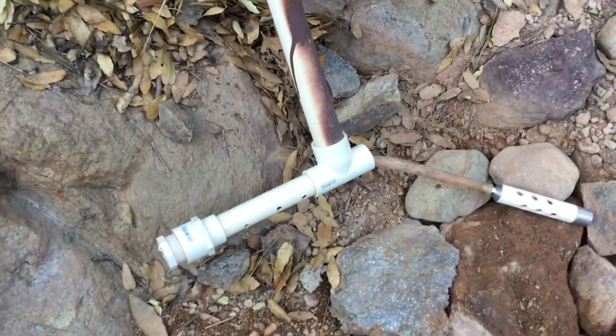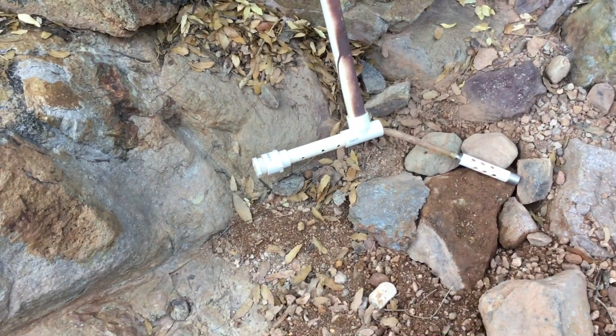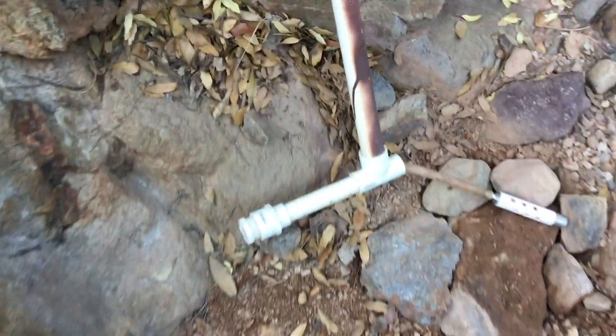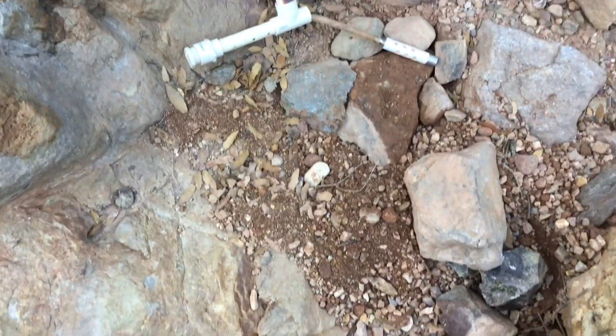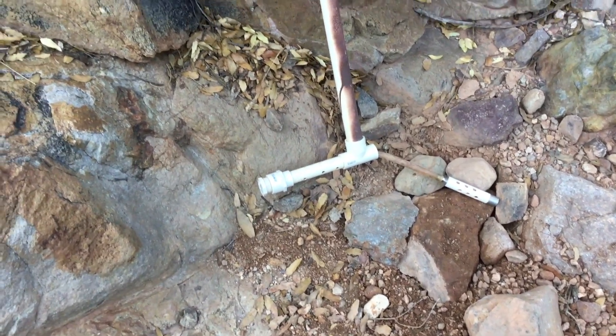The sampler inlet is lower than the tube. It would be nice if we could get it even a little bit lower. I put it on some rocks so that it's not sucking up dirt, and I've confirmed that the light is on. You can see a red tinge right there — that's the light after I put this whole thing together. You can still see that it's functional, and I'm going to leave this the way it is for now. You can see that there was flow here — the ground is wet — but I'm not going to mess around with this anymore until I come out next time.